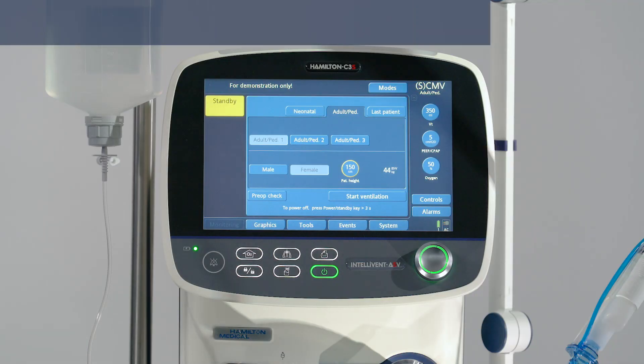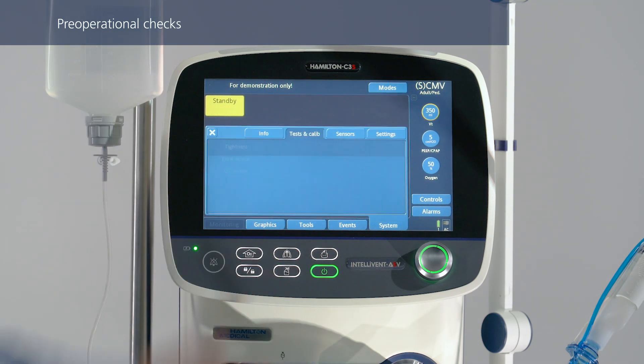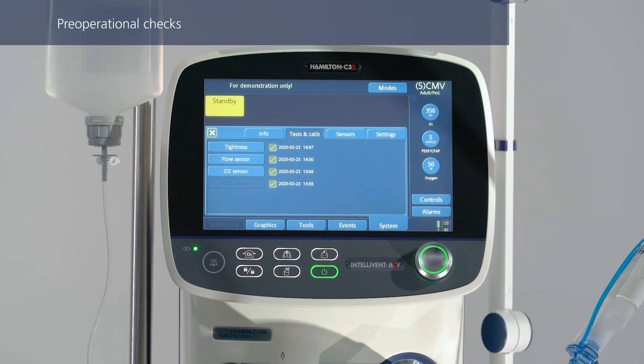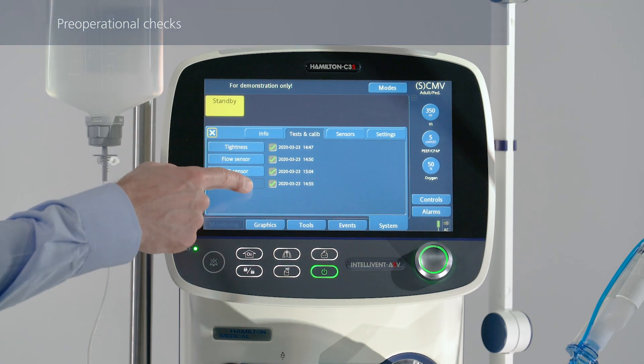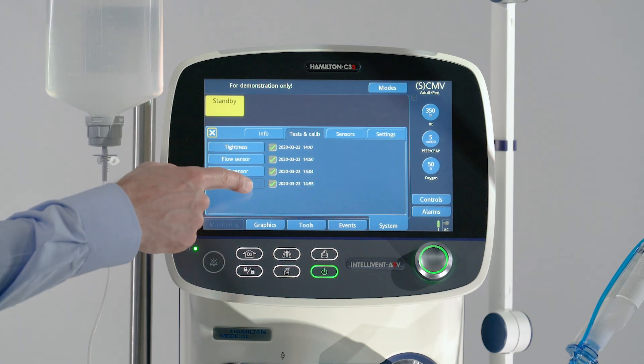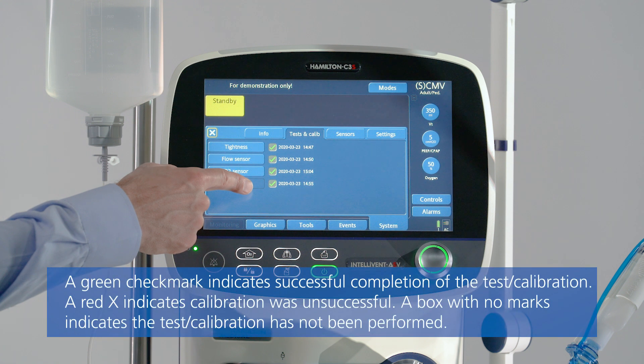If you have already performed the pre-operational checks, you don't need to repeat them. The test results are stored in the ventilator's memory, even when it is turned off. Make sure that the setup you calibrated is not changed or altered while the ventilator is in storage. If you haven't already done so, perform the pre-operational checks now.